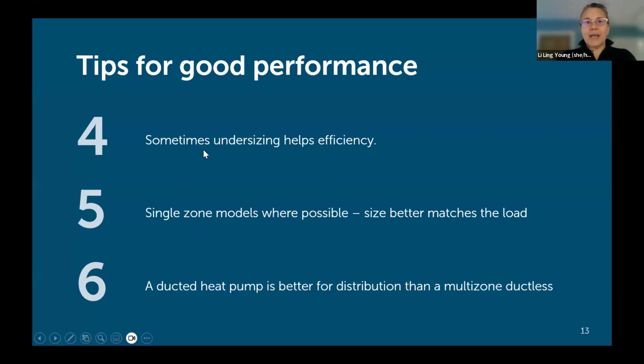So consider undersizing if it helps efficiency. Use single zone models, and the reason for this is that multi-zone models do not come in small sizes. I already showed you what can happen if your system is oversized, you get bad part load performance. So if you have to choose a big one, like let's say the multi-zone you're considering is 36,000 BTUs an hour, that might be too big for what you need, but you needed 3 zones so you had to get to 36. That's a setup for bad efficiency. So use single zones where possible, because they can be better sized to match the load.